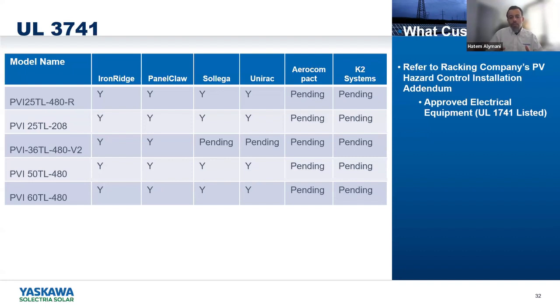But at the same time, you just have to make sure that you discuss all that we discussed. You need to make sure that the AHJ is accepting it, you have the perfect roof, and we are certified, because if you move forward assuming, then you're going to have a lot of issues. You're not going to pass the inspection, and you're going to delay, and you'll have to take all the modules and retrofit the rapid shutdown. It's going to be a headache. So it's better to be prepared. Better safe than sorry.